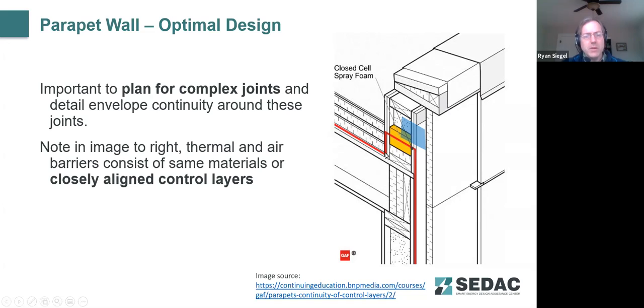And so trying to align that thermal control layer to the best of one's ability. The thermal and air control layers do need to be closely aligned and in intimate contact with one another. Either the thermal control layer needs to be air impermeable, or you do need to have those two control layers touching to prevent air from passing through the thermal layer and allowing moisture and other coolness to pass through.